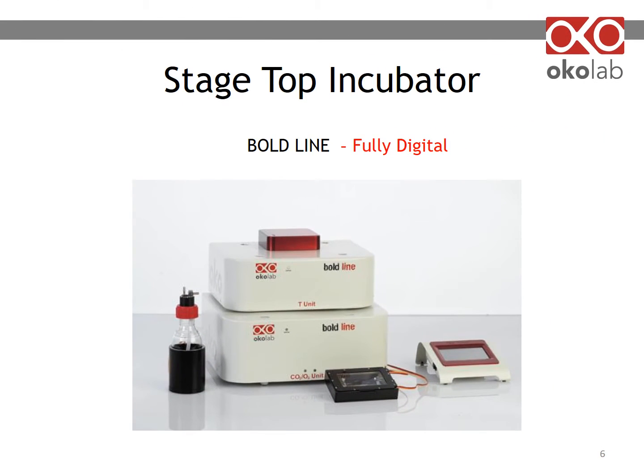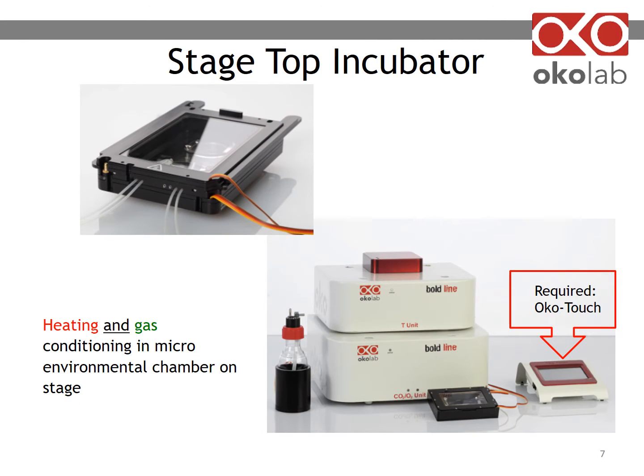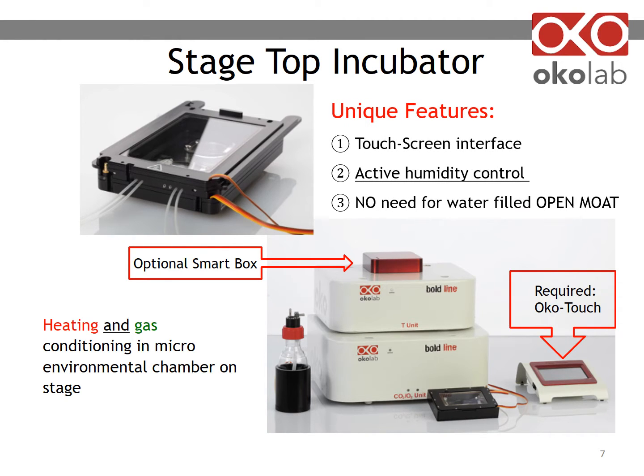This slide shows the bold-line fully digital stagetop system. In the image on the right-hand side, you can see a stack of controllers — they're digital for temperature and gas. Each stack requires one touchscreen interface. Humidity is controlled in an active way; it involves a bottle with humidity sensor lid and a heated base. Because of this design, the microenvironmental chamber does not have an open moat with water — we designed it this way for safety reasons to avoid spilling water in the nose piece.